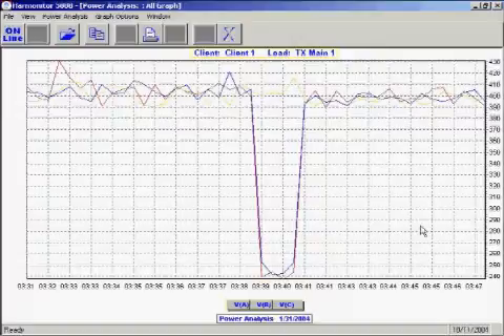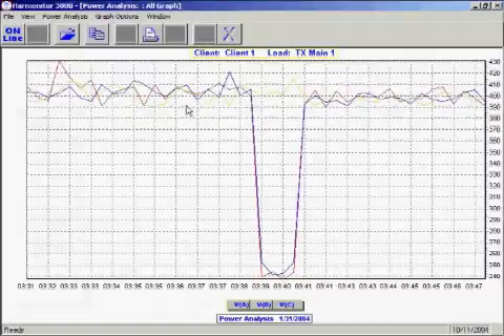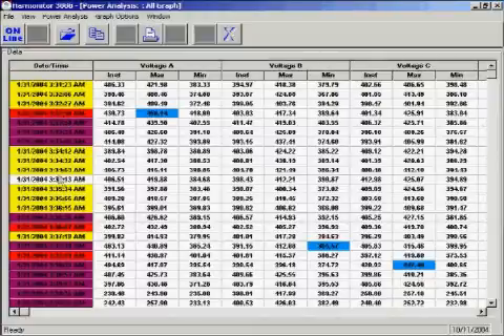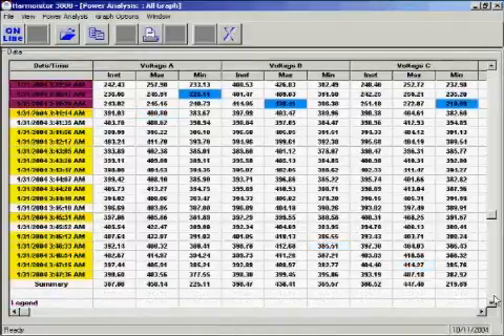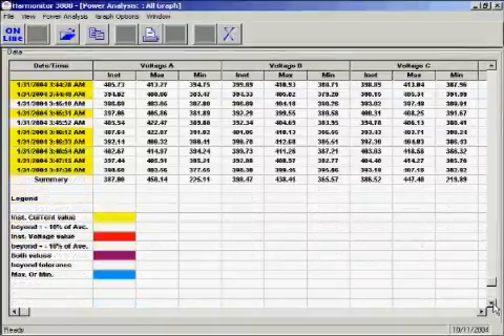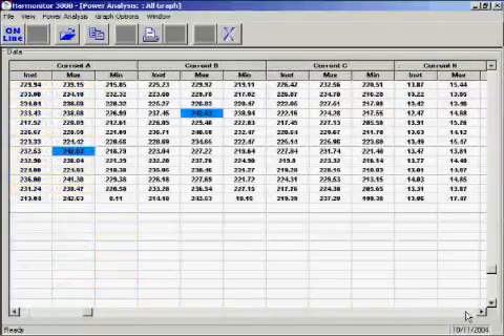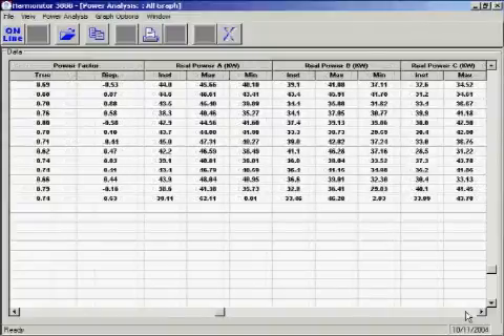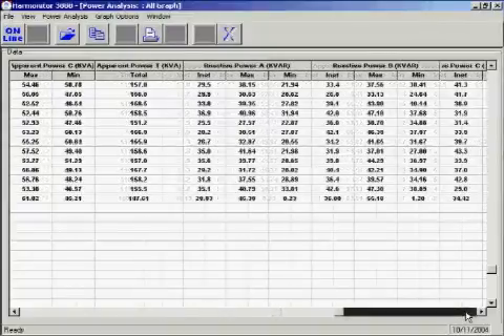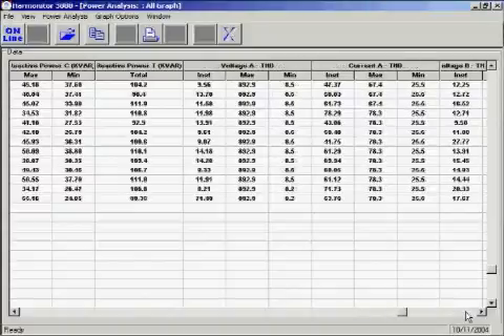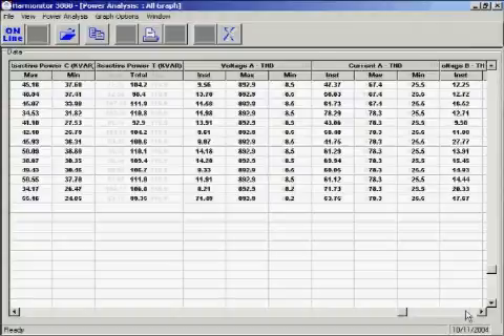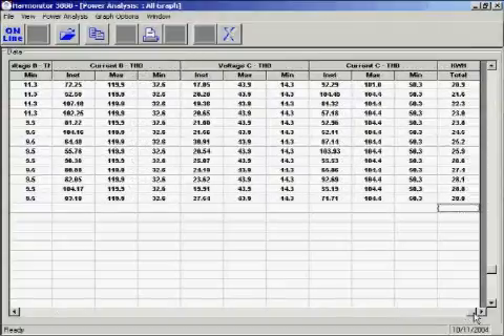Seen here is a voltage graph over time of all three phases. To see data in a tabular form, double-click on the graph. Here we see all the calculated values. The far left column has a timestamp for each individual sample. These values are color-coded to indicate when events occurred. For more information, please refer to the legend at the bottom of the spreadsheet. Following the timestamp are individually calculated values for each phase for voltage, current, power factor, real power, apparent power, reactive power, total harmonic distortion for both voltage and current, and finally, kilowatt hour.